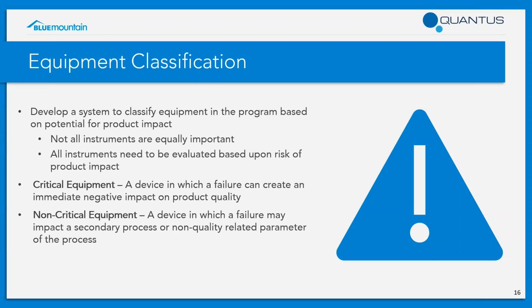Yeah, that is a really interesting outcome on that poll, because when we're visiting customers, we're finding that what we're calling equipment classifications or criticality assessments is one of the more underutilized tools in a program. And it is a very important process because not all equipment or instruments are created equally or equally important to the process. And companies can really waste a lot of time and effort investigating out of tolerances on equipment that's not critical. So defining those equipment classifications can really lead to more effective out of tolerance investigations. And the classification of these instruments is typically an output of your risk assessment that we're going to cover a little later.